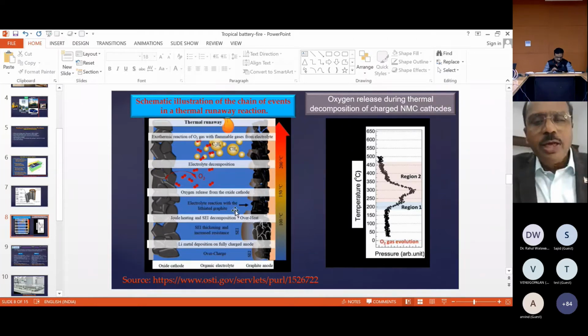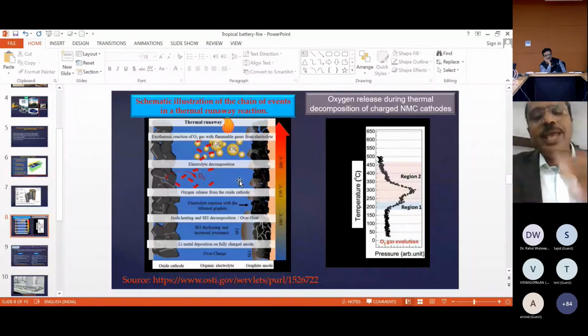The electrolyte reacts with the lithiated carbon because the SEI is gone, so it starts reacting with carbon, further increasing the temperature with some gases. Oxygen is released from the cathode by 150 degrees, which enhances the reaction and electrolyte decomposition. You start getting alkane gases like methane, ethane and others, and they blow up, leading finally to fire. So by 200 to 250 degrees centigrade internally, that leads to fire.